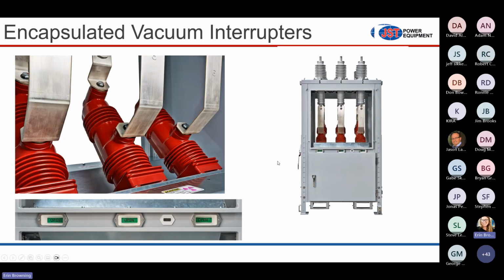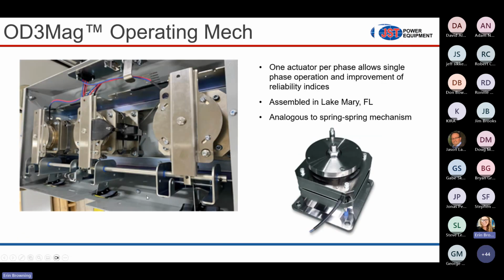Here's a real life image of the circuit breaker poles up close. If you've been to our factory in Lake Mary, you've seen these poles on the floor. The pole itself is outsourced. It's the only component that we get from outside of the USA. Once it's in the factory, it's married with the actuator, which is magnetic and, once again, completely assembled in Lake Mary. And this is the circuit breaker tray itself with the actuators, one per phase, mounted to it. This whole tray assembly module is made in Lake Mary.